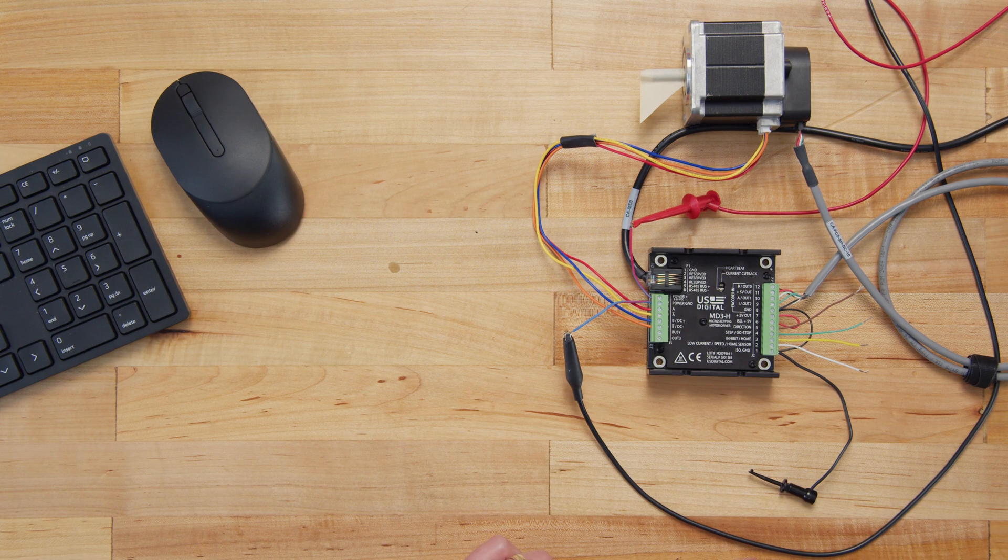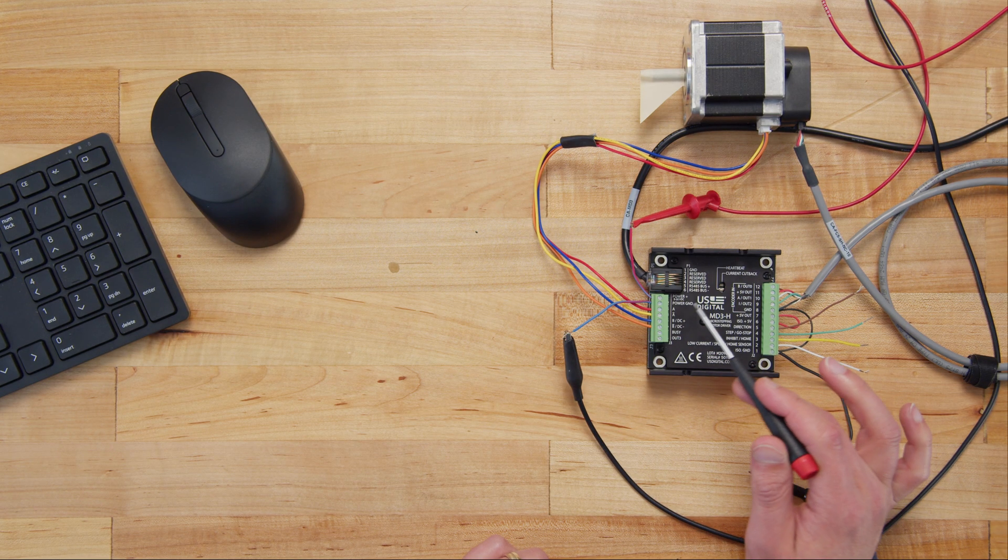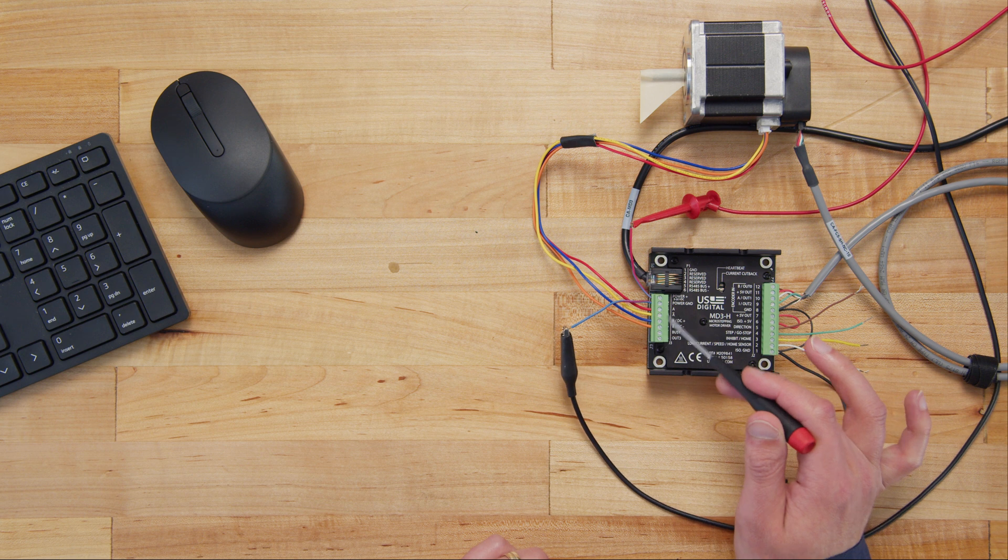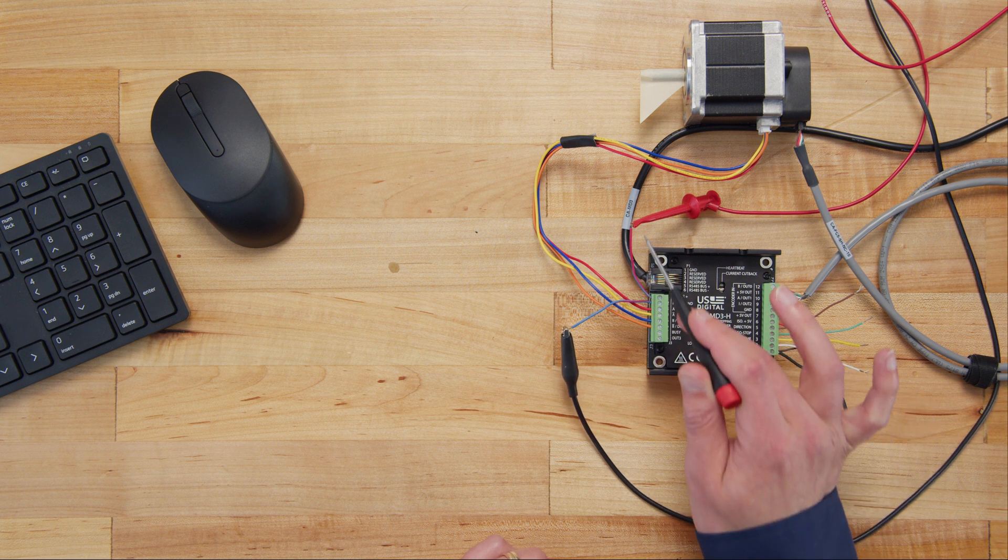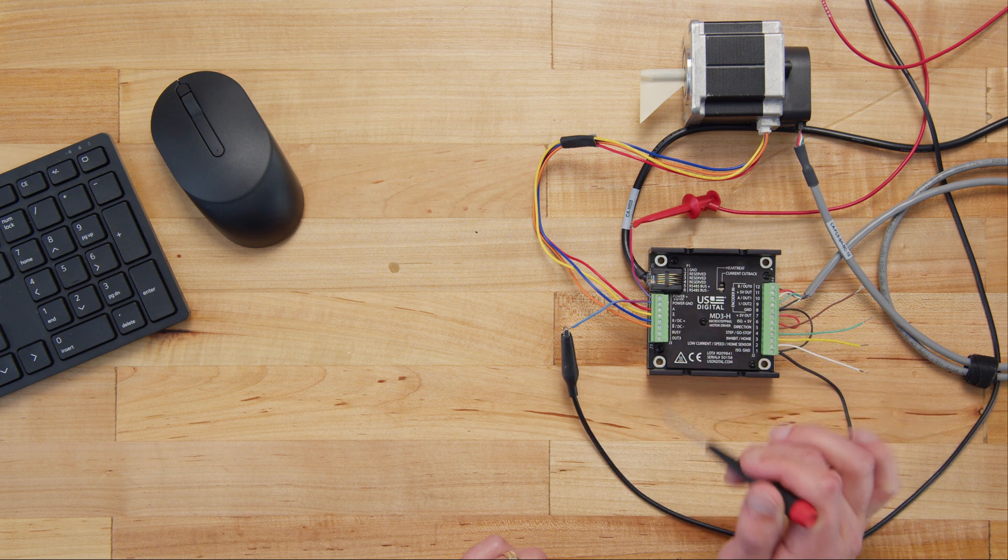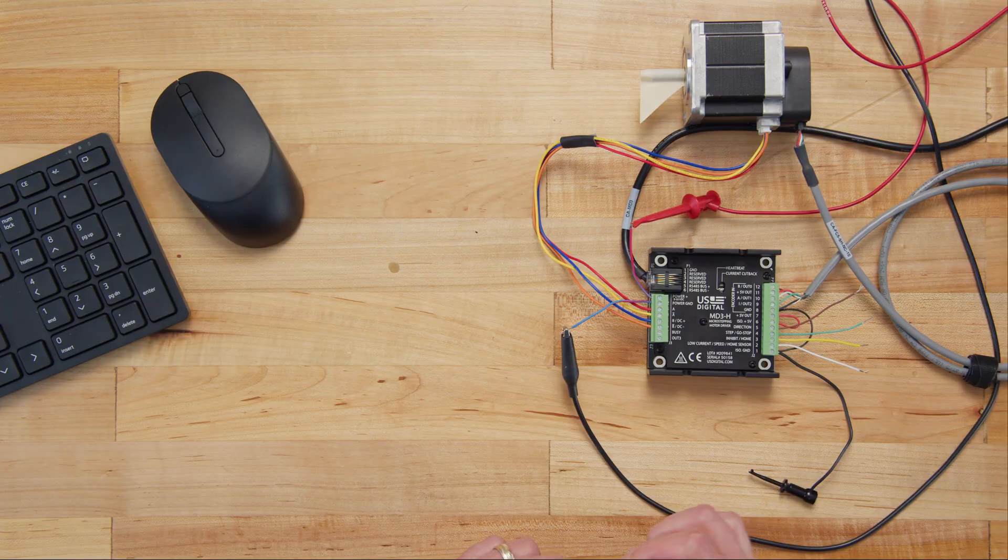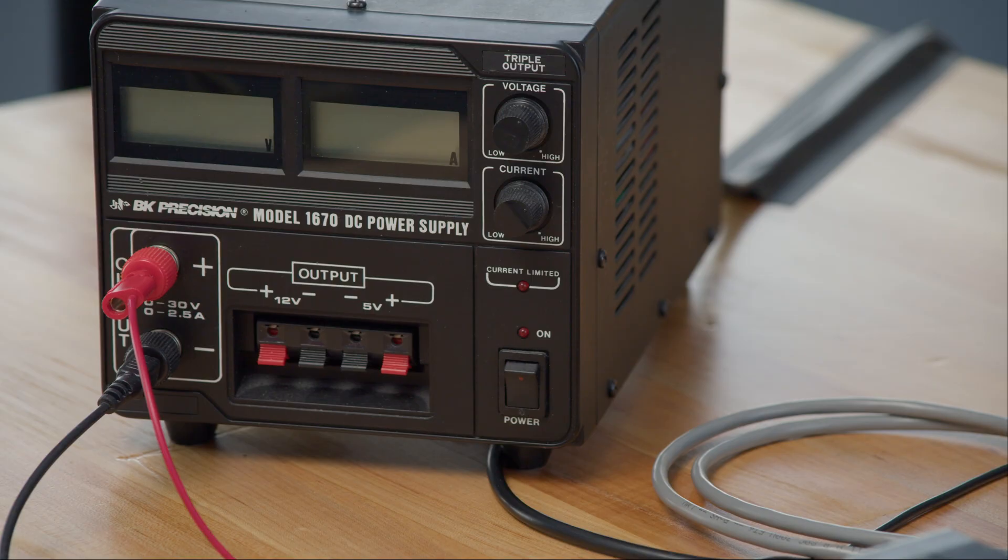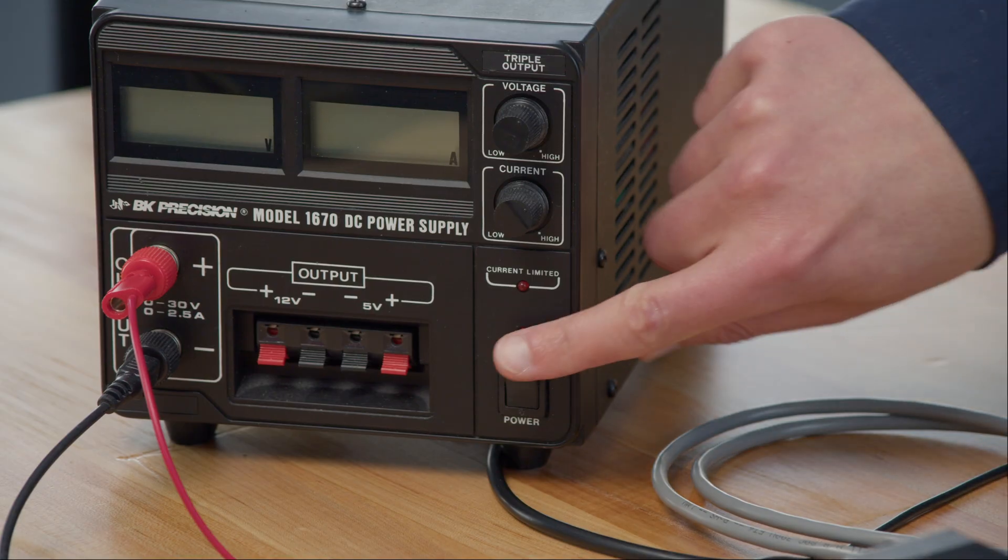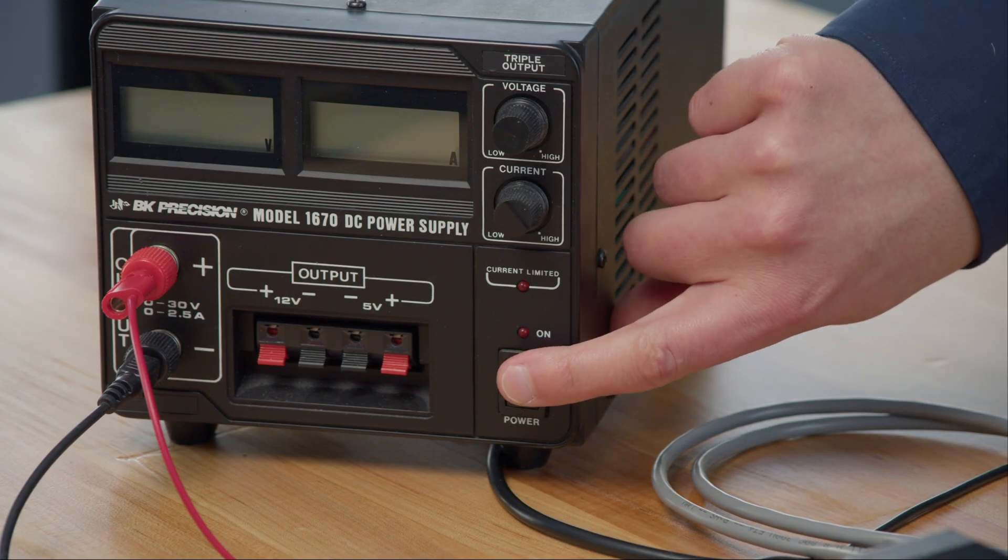This is probably a good time to mention: do not connect or disconnect the motor leads when the MD3 is powered. Make sure that all connections are made and the J3 is plugged in before applying the main power. Do not unplug the J3 connector when the drive is powered. Failure to do so may damage the drive.